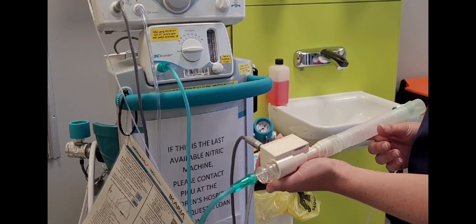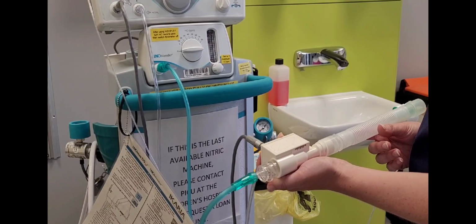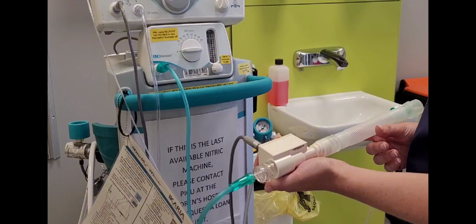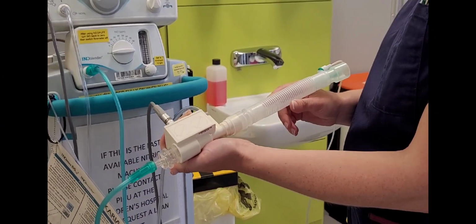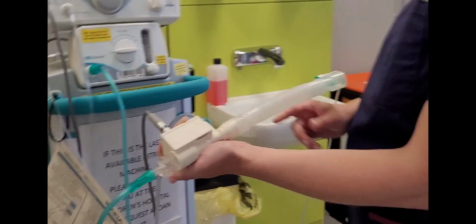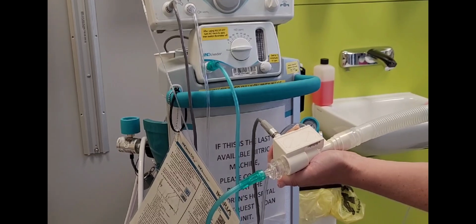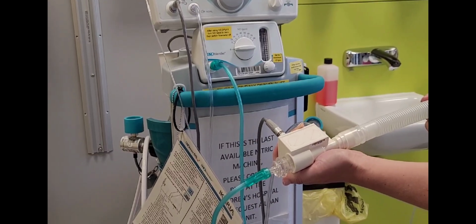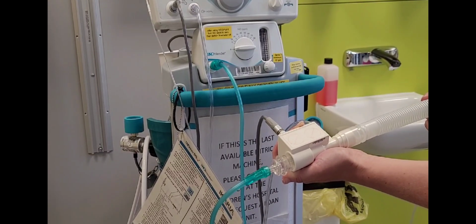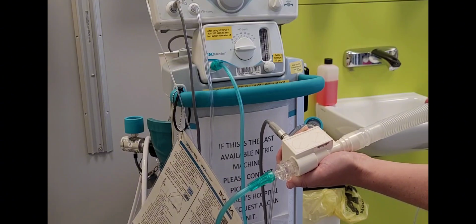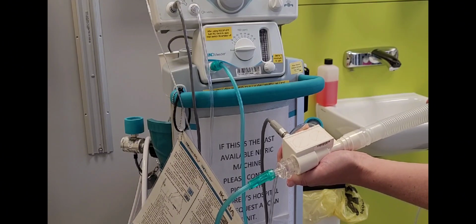To set the machine up, slide the filter into the back of the INOmax, then set up the rest of the equipment as demonstrated here. Connect the injector module cable to the front, like so. Connect the patient gas sample line to the sample connector and connect the oxygen tubing to the wall or a cylinder. Once the equipment has been set up, you are now ready to test it.